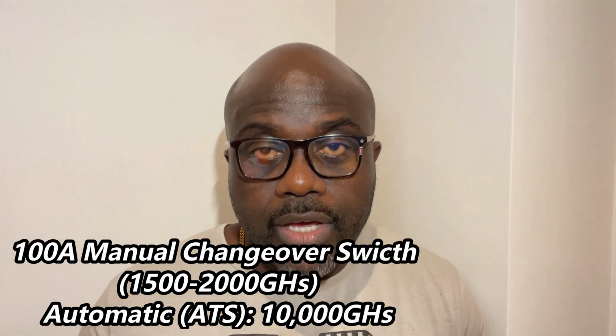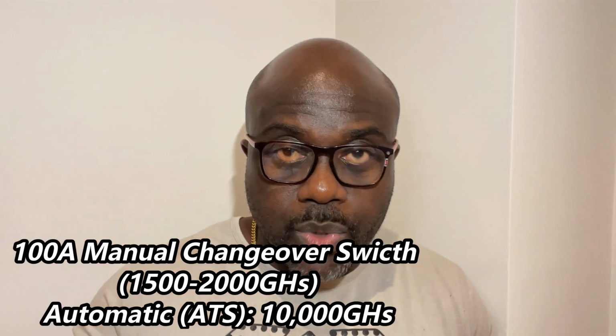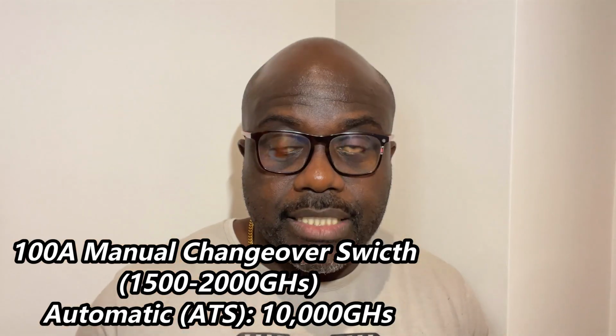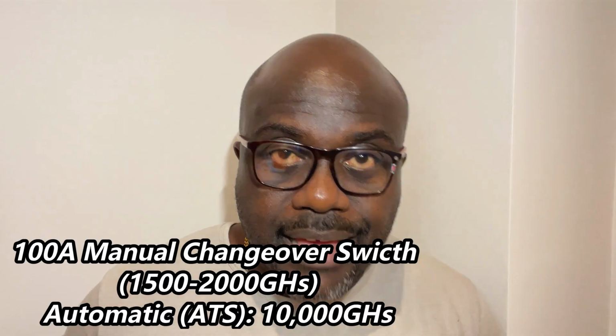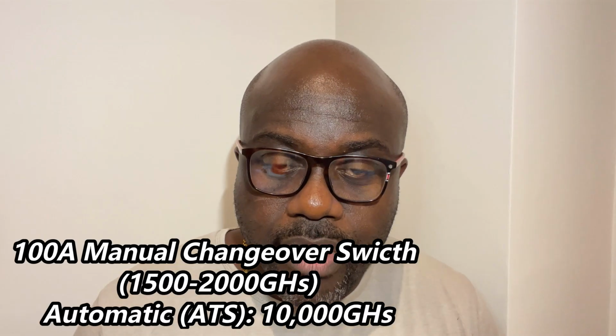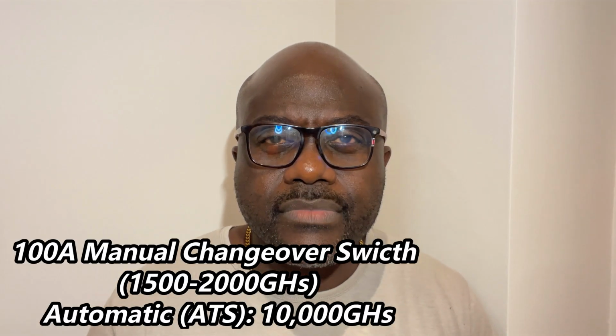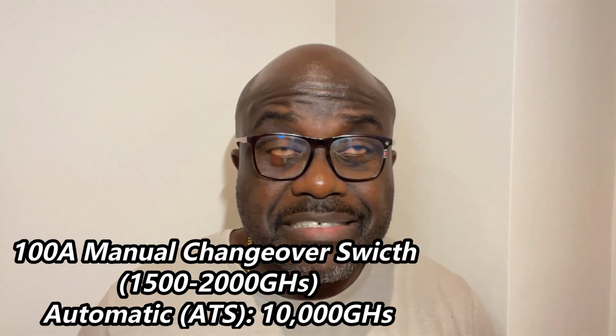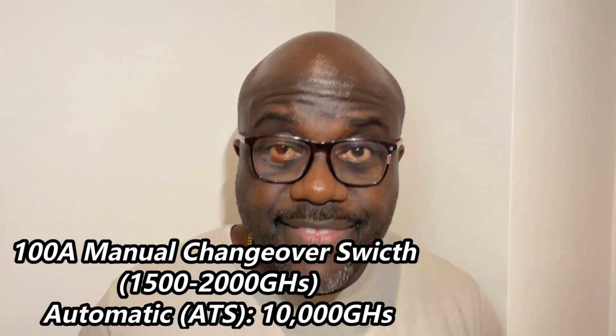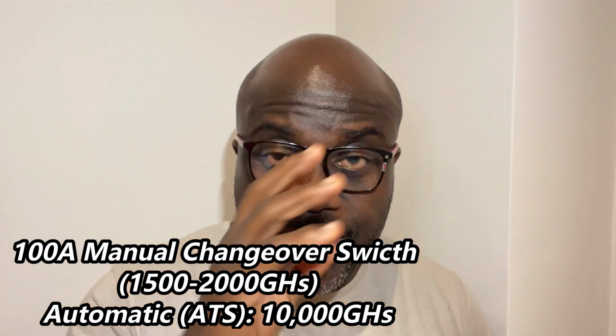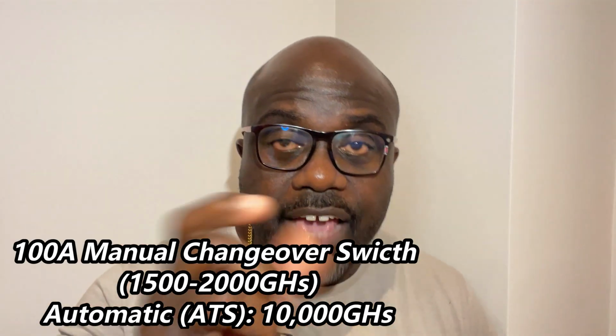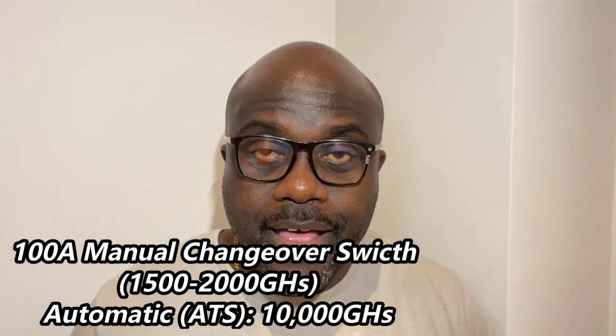Between 1,500 cedis and then 2,000 cedis, depending on the brand. Okay, if we talk about an automatic changeover switch, that uses contactors. The last time I bought one in Ghana for a client, I think it was around Tema, it was about 10,000 cedis, a fully complete automated unit. So that's 5 times the cost. It depends on how many you have in your design, but that's 5 times the cost, but you're paying for convenience. And convenience is great.